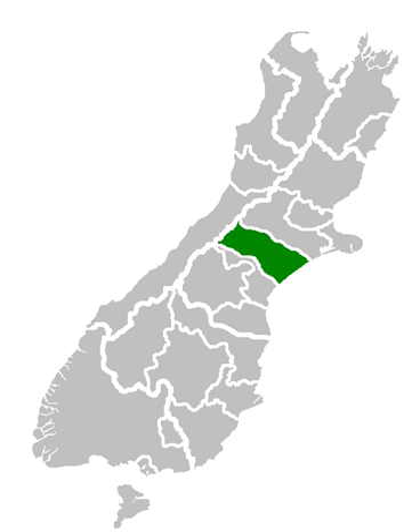A 33/66 kilovolt transformer at EA Networks' Elgin Zone substation, located next to Transpower's substation, provides a connection between the two supplies. The 33 kilovolt supply from Elgin is used to supply the entire Ashburton Township from the Ashburton Zone substation on the site of the former Transpower 110 kilovolt Ashburton substation and Northtown substation, as well as three major industrial customers at Fairton and Seafield.